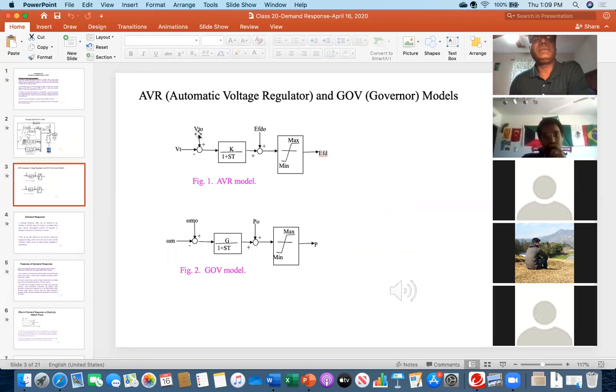In case of the AVR, automatic voltage regulator, you need the error signal. VT0 is the reference signal, reference voltage, for example 100 volt. And VT is the measured voltage from the system. So you check if there is any difference or not. If there is any difference, it will be processed through this control system, and finally it will produce the field voltage. You remember I told you EFD means field voltage. Basically, the automatic voltage regulator system controls the field voltage, which ultimately controls any voltage error.